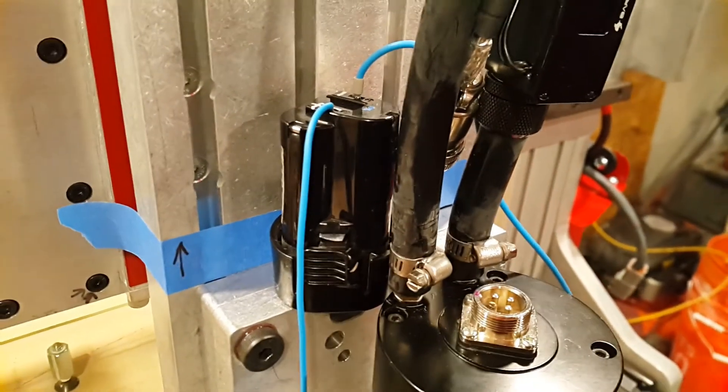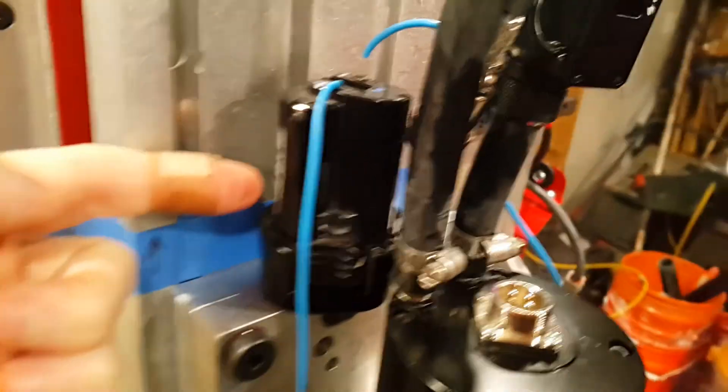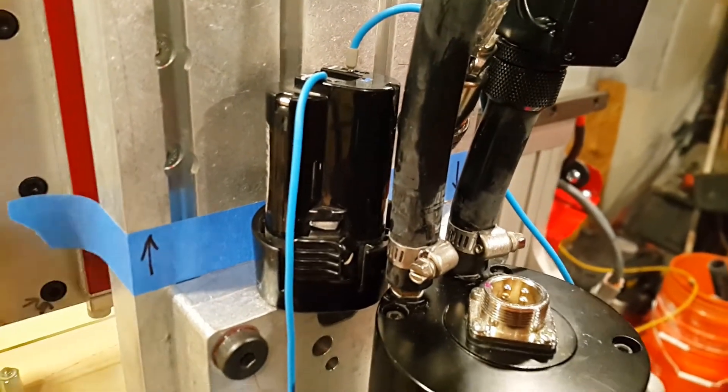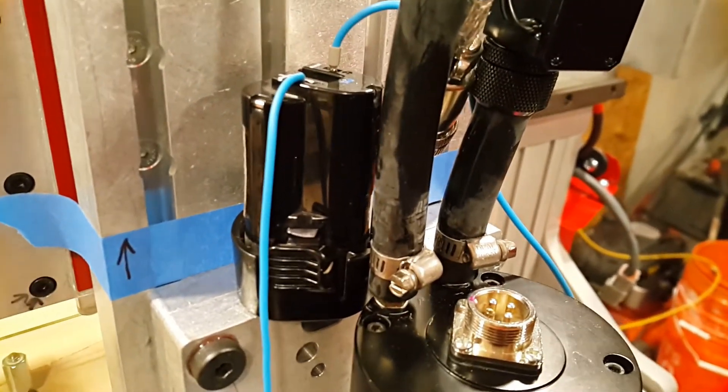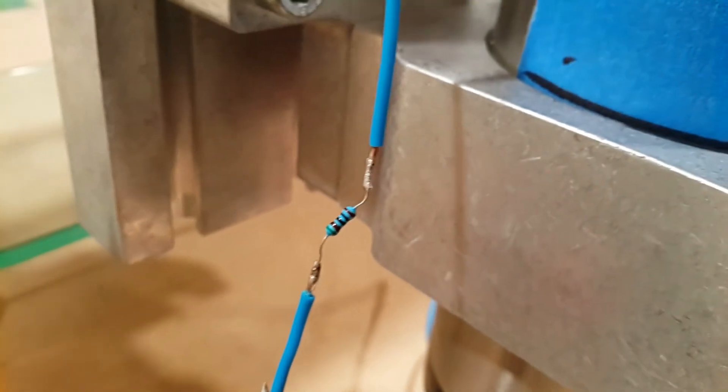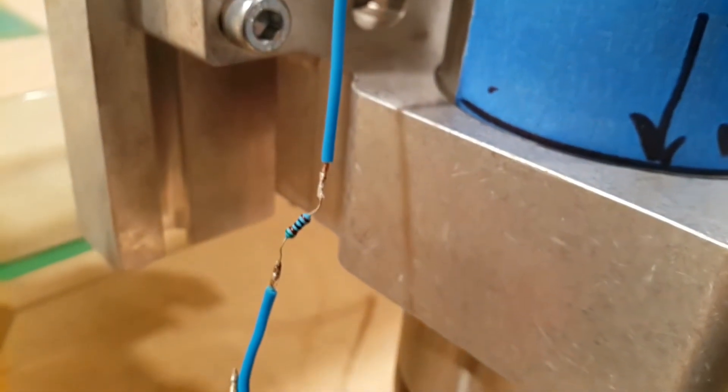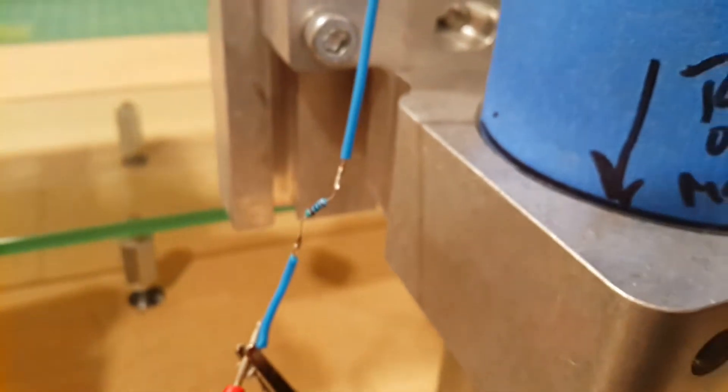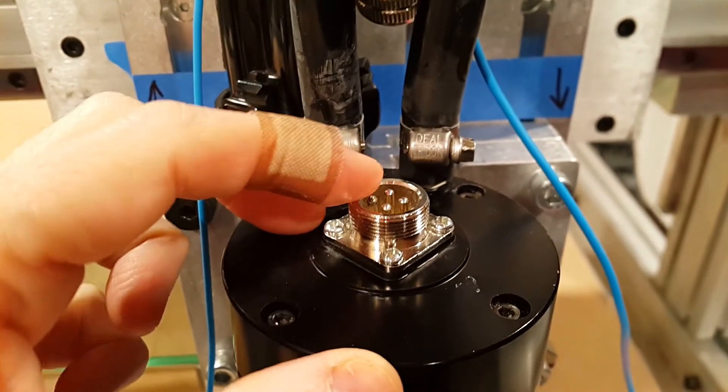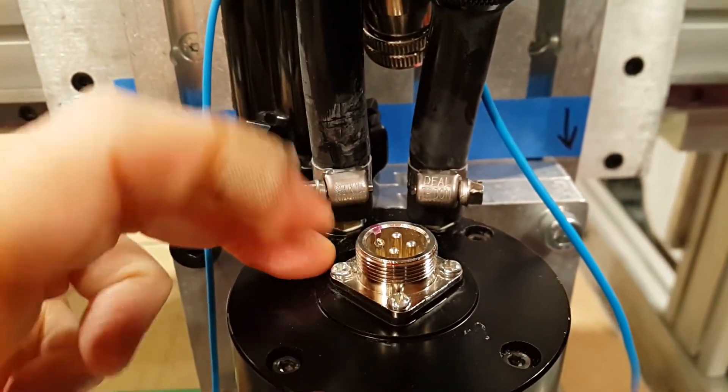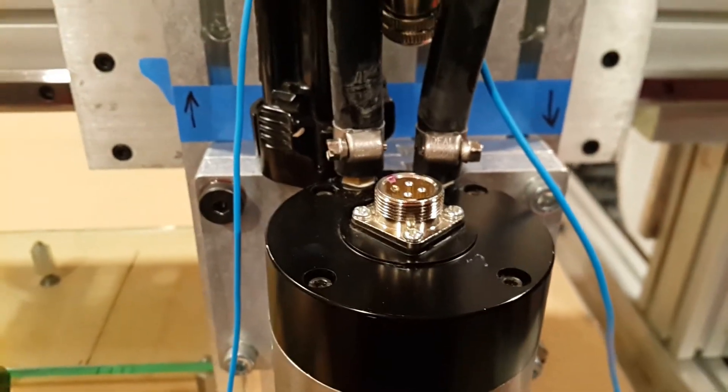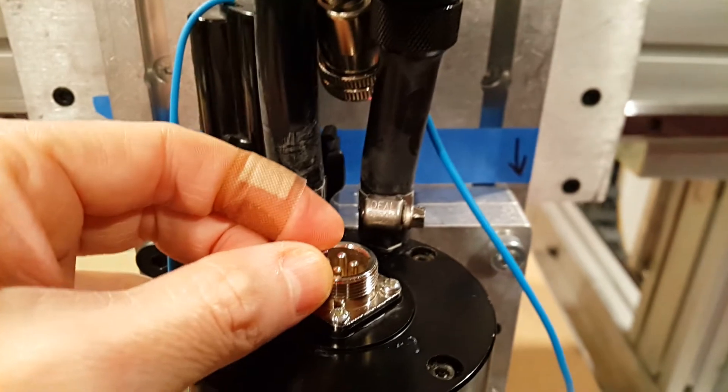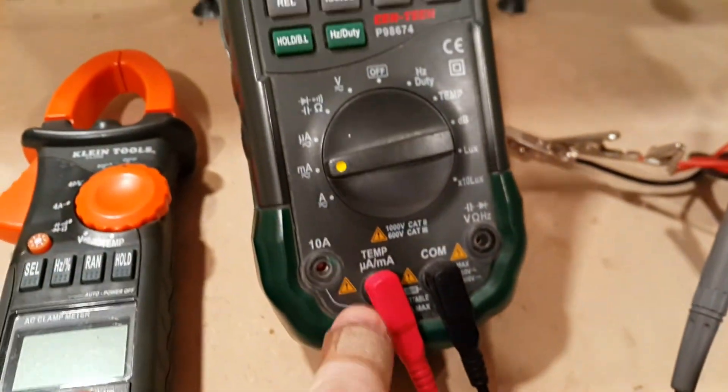Here's the setup. This is a 12-volt DC battery from a Makita drill. It's going to be our voltage source for this test. I have it wired up through a 500-ohm resistor, which is going to limit the current to be quite small. I've measured it already at 23 milliamps. What we're going to be doing here is sending a small current through one of the windings, one winding at a time, and then we're going to measure the voltage drop across that with the other meter. So one meter is set up to do milliamps and it's actually in line as part of the circuit.